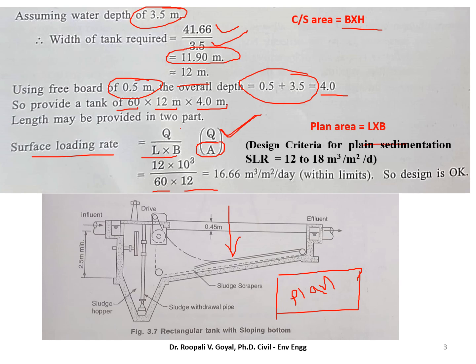Length into breadth is 12 by 60, that is 720 meter square. So we are getting 16.66 meter cube per meter square per day. And this is within limit. And as we know that it should be in the range. And here we have designed length and breadth and height, that is depth, and 0.5 meter is your extra space that is your freeboard, and this design is okay because the surface loading rate is coming within limit.